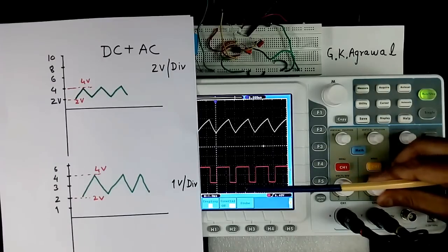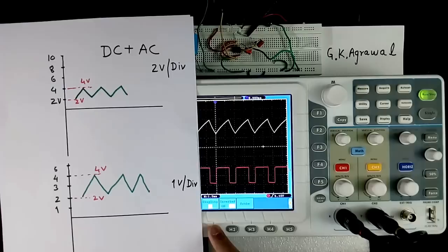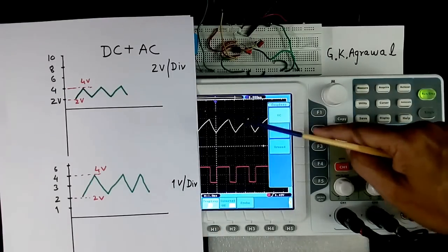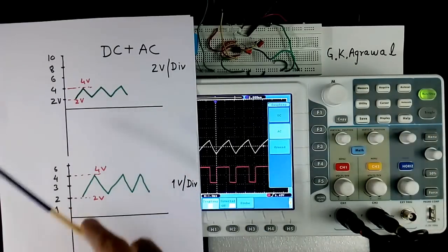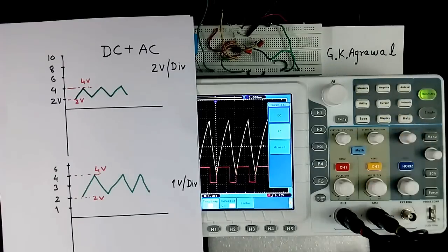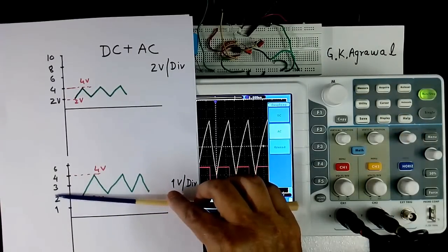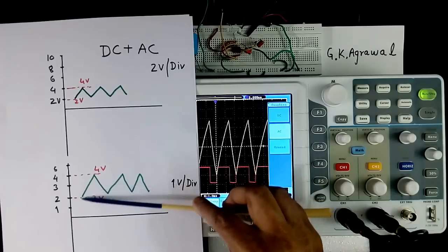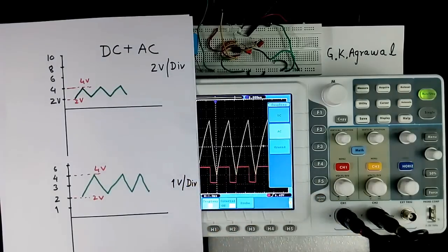This is coupling. I select AC coupling. Now DC has gone. Only AC. Now if you make like this, the DC problem will not be there. This AC alone you can extend the scale.